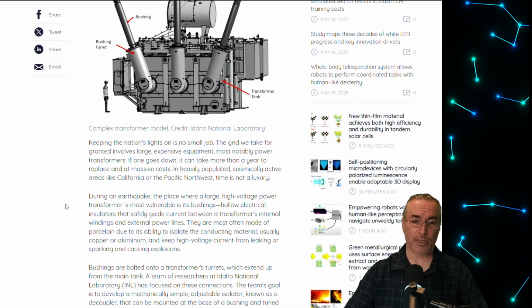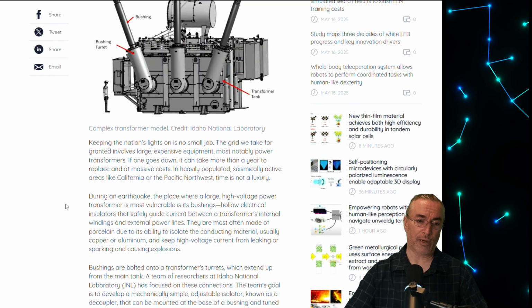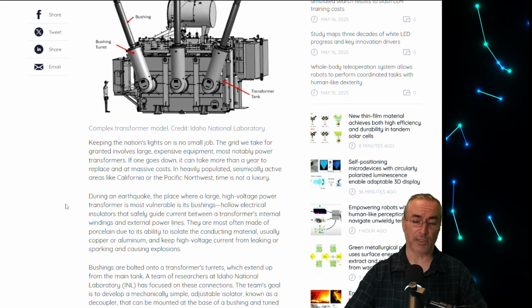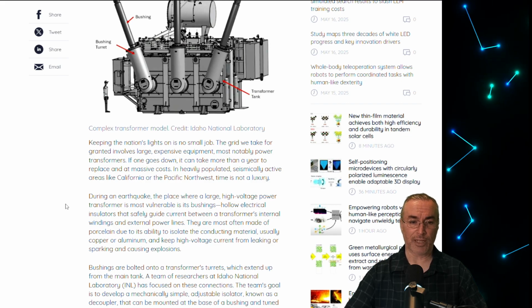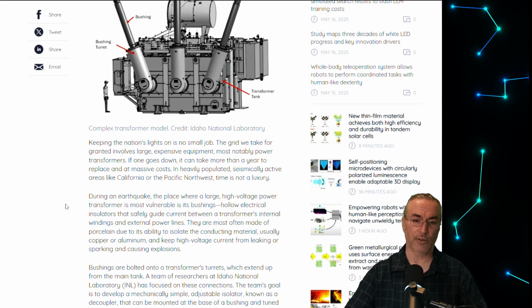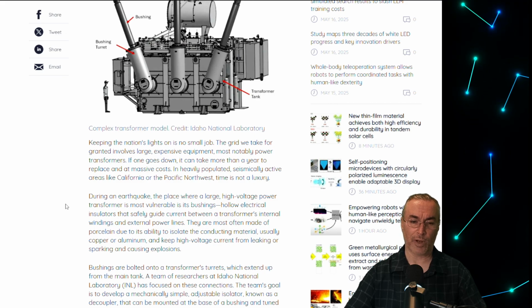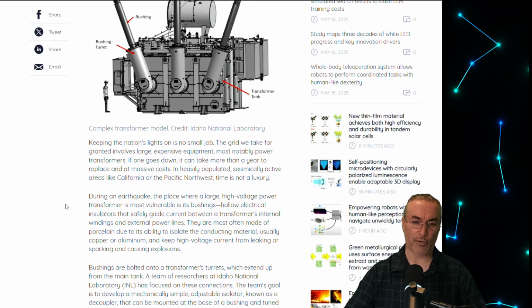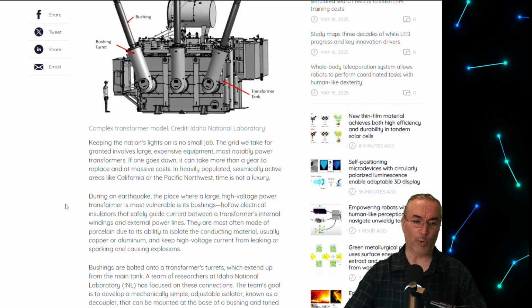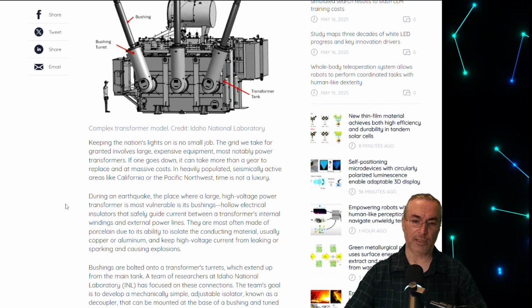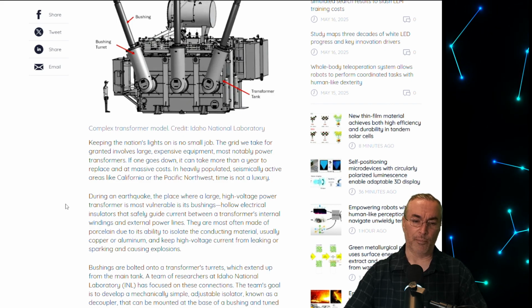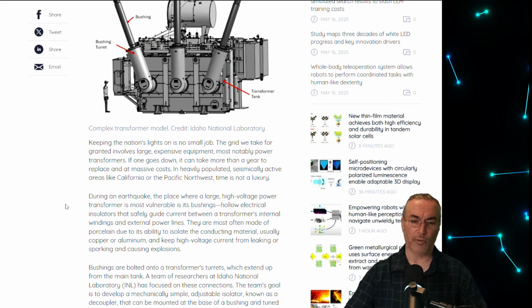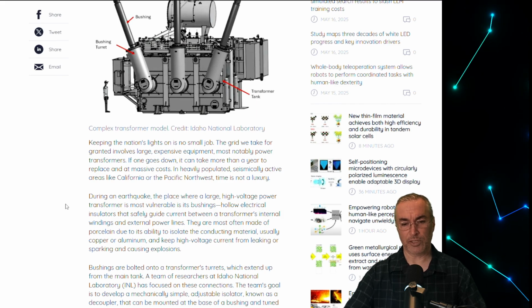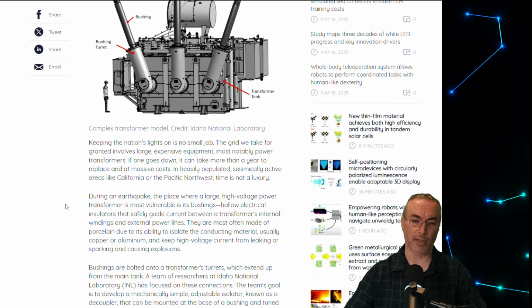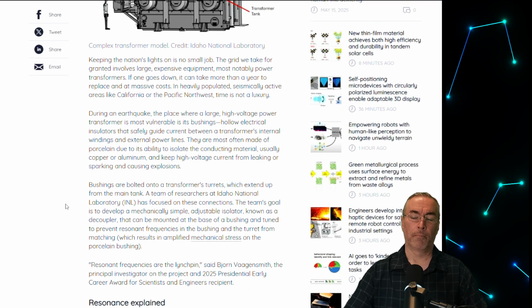During an earthquake, the place where a large high voltage power transformer is most vulnerable is its bushings, hollow electrical insulators that safely guide current between a transformer's internal windings and the external power lines. They're most often made of porcelain due to its ability to isolate the conducting material, usually copper or aluminum, and keep high voltage current from leaking or sparking and causing explosions.